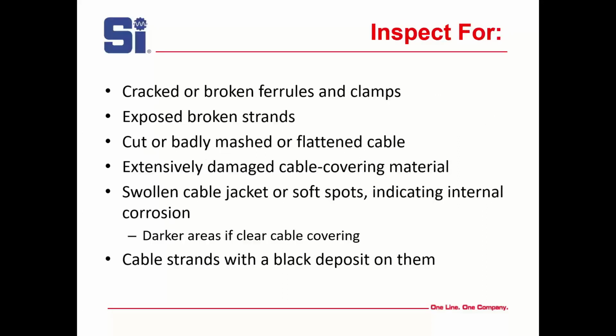So when you inspect it, of course, look for broken ferrules or clamps, exposed, broken strands, and what happens as these strands break, you're losing ground capability. So you've got to have them all. Cut or badly mashed or flattened cable, that means something inside is probably broken. Extensively damaged cable covering, because that's going to allow moisture to come in and corrode the cable. Swollen cable jacket or soft spots, that means you've already got internal corrosion. And of course, if you have a clear coating, you can see dark areas. And then outside cable strands with black deposits on them.